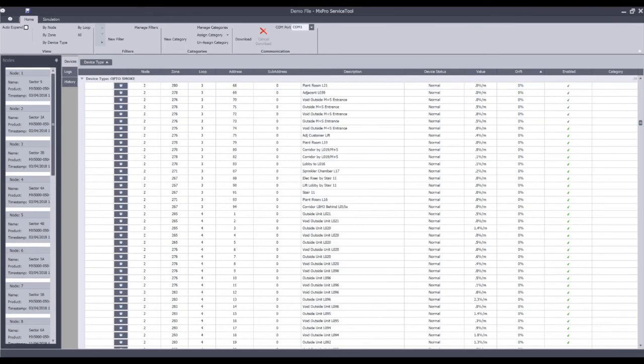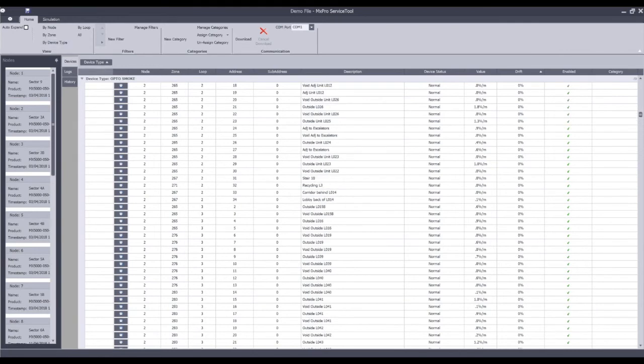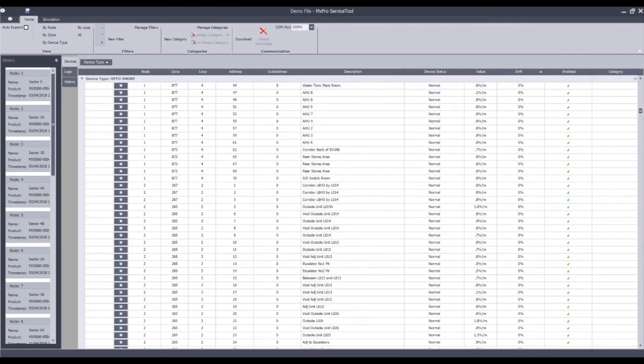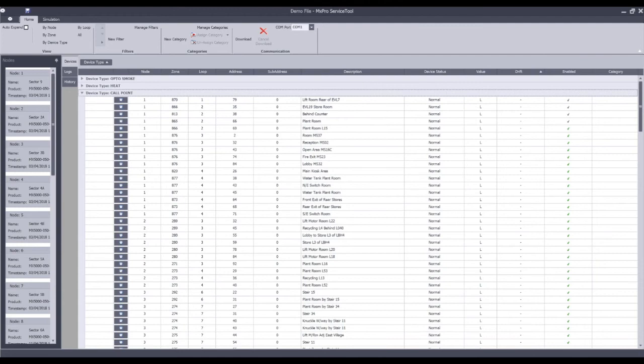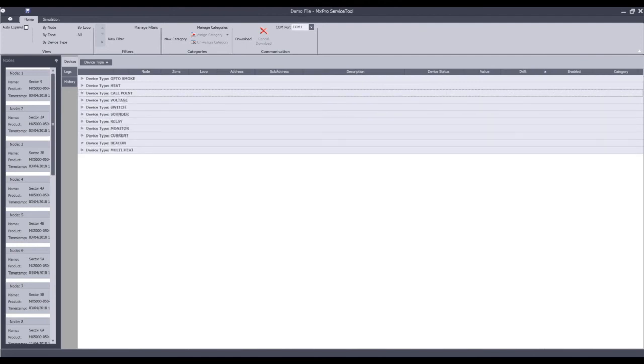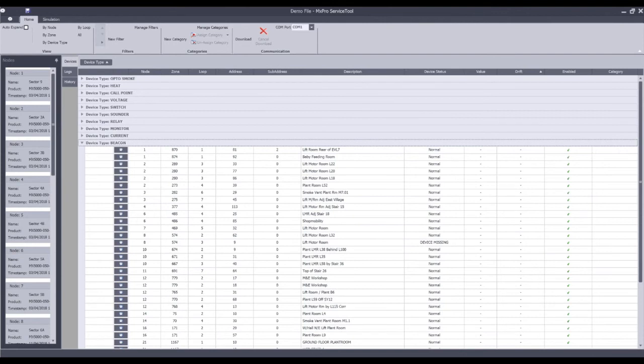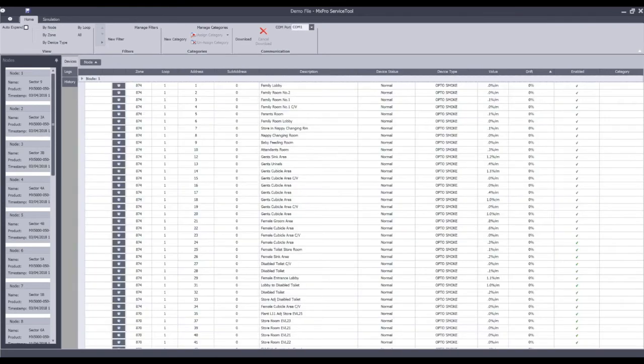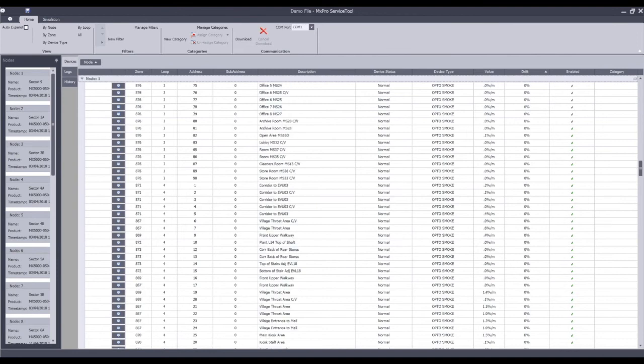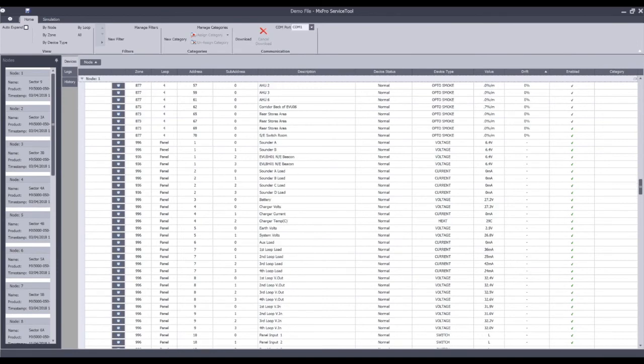That's basically the device overview — you can scroll down the list. I've currently only got smoke detectors selected. If I wanted to change the device type, I can revisit the selection and go to call points, or if I wanted to, I can go to the status of beacons — it's just a shortcut so you can see different device types at a glance. You can also filter by node, by zone, by device type. Clicking on a node gives you everything including panel hardware, loops one, two, three, four, panel sounder circuits, your earth monitor, your charger, your auxiliary supply, and so on.